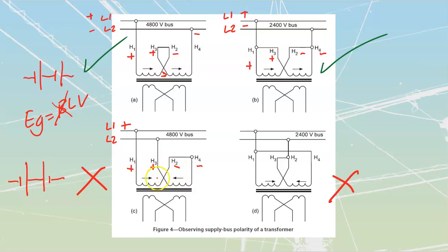In other words, we're going to cancel out the flux inside here. With no flux, we generate no counter EMF, and this is basically the equivalent of bolting a line across from there to there. It's going to be a dead short. It's going to be dramatic: violent arcs, explosions, people yelling, people getting fired, probably you if you're the one that connected it. It's just something you want to stay away from.